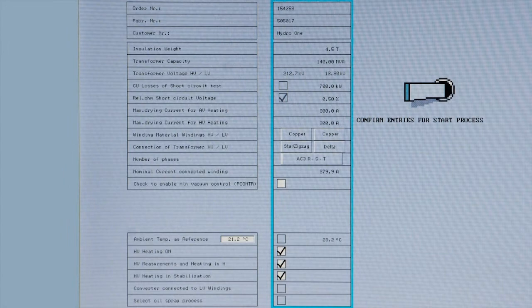Relative ohm short circuit voltage, μR, can be entered as a percent so that the copper losses can be calculated. Maximum drying current for the HV heating is the absolutely maximum current that will not be exceeded by the LFH plant, even if the CF factor is asking for more current. It is used as a design safety factor to prevent damage to the transformer. The value is entered as amperes.